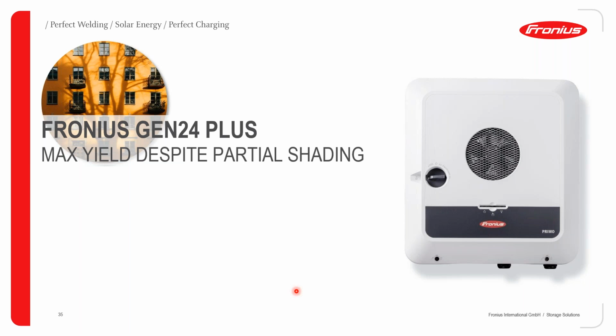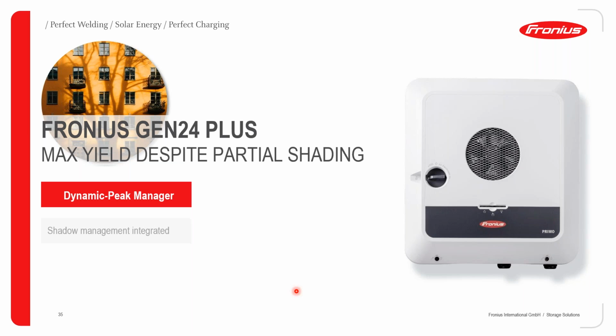When you look at the Fronius Gen 24 Plus, it's also important to emphasize that we are offering this inverter with something we call the dynamic peak manager. This assists with production despite partial shading conditions. As you know, shading is one of the most detrimental aspects of a PV installation and can significantly reduce your PV output. But all Fronius inverters, the Snap inverters and now the Gen 24 inverters, have the dynamic peak manager integrated. The dynamic peak manager basically allows shade management to ensure that even in partial shading conditions, the inverter continues to operate at the highest level possible.